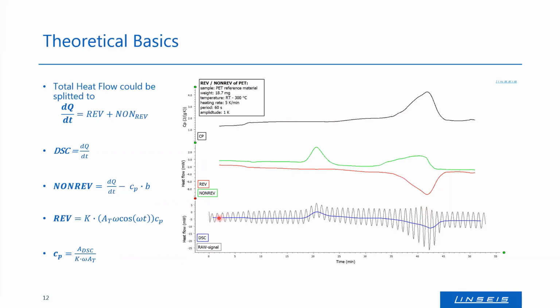And here again, you can see the DSC signal you can receive and also the raw signal with the modulation. The CP itself is the amplitude of the DSC signal with a calibration factor, omega, and the amplitude of our modulation, what you can see here at the bottom of this slide.